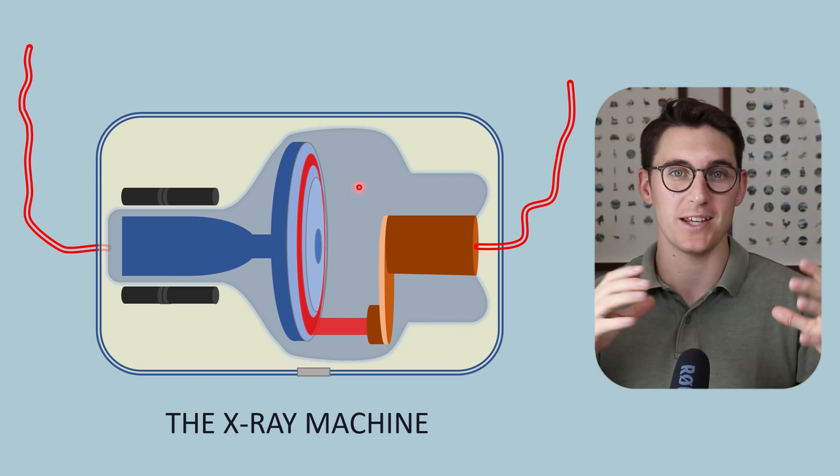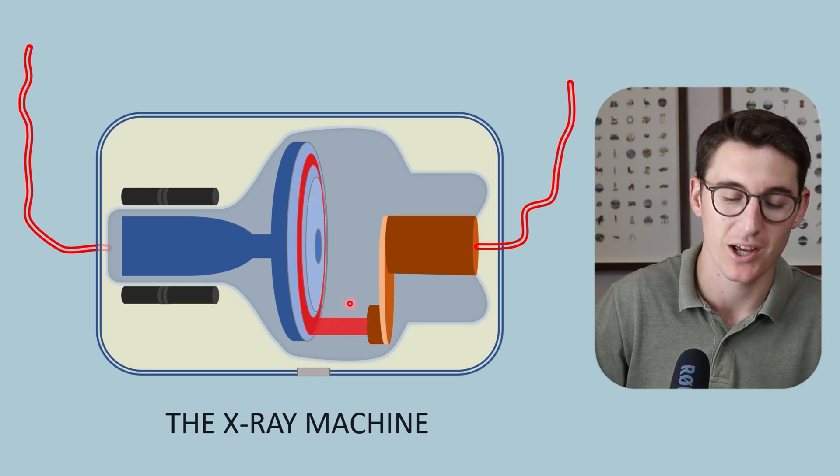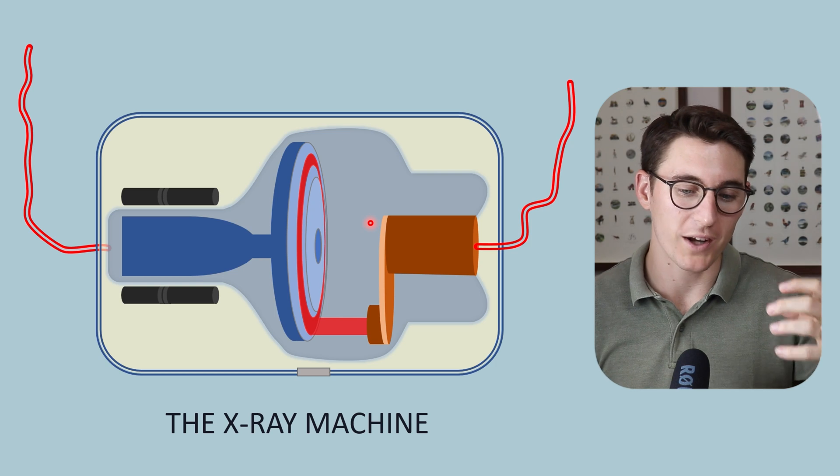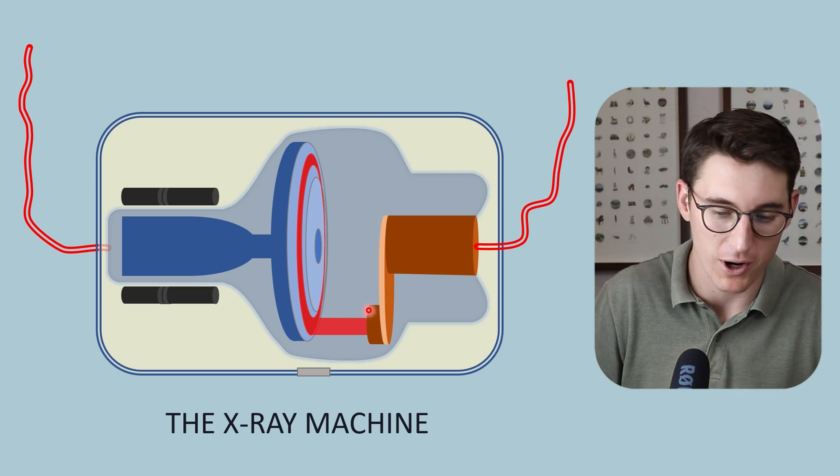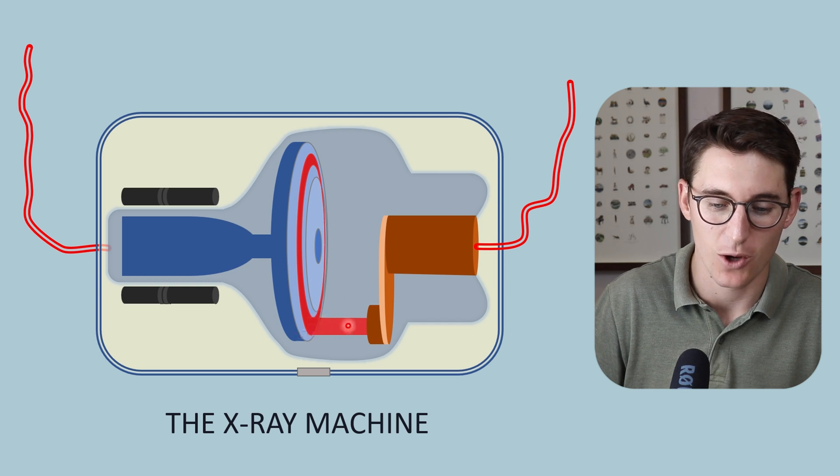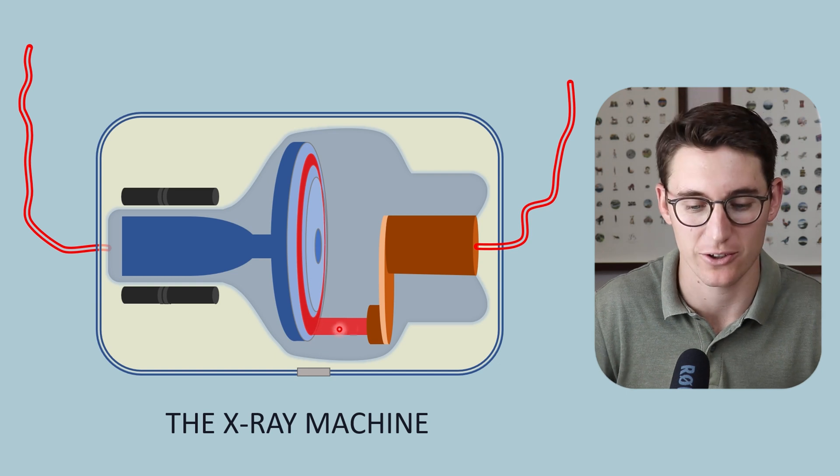There is no air within this glass envelope, and that allows our electrons to pass towards our anode unobstructed. We don't want those electrons to interact with any other atoms or molecules prior to striking the anode. We want all of that energy to be deposited into our actual focal spot on the anode.